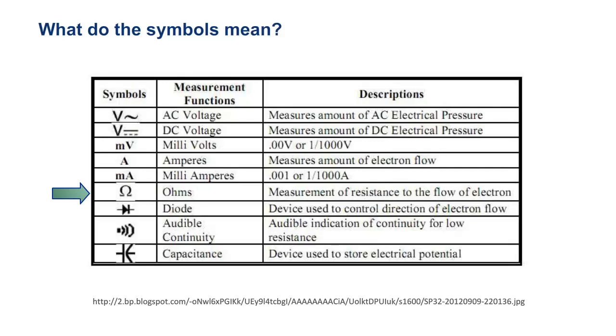The other way we use it is with a grounding test. And there we want to see big numbers because we don't want the current to be able to escape. So we want to see large numbers. How large? In the millions. If I'm measuring each leg to ground, for example on an above ground motor, I'd like to see 5 million ohms or higher.